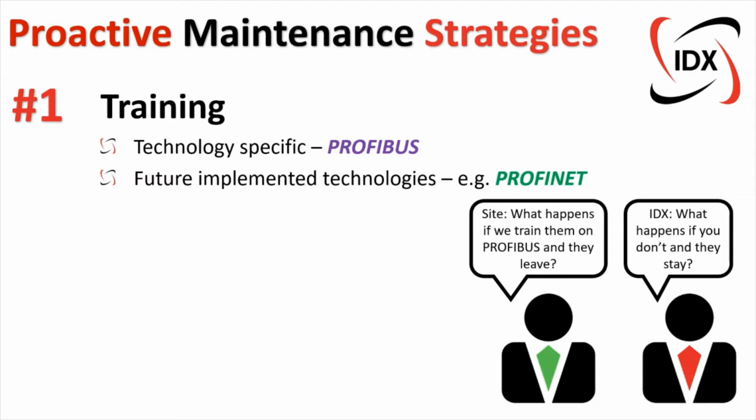And that's pretty important, because I think one of the biggest downfalls which PROFIBUS has suffered in the past is that it is installed badly outside of the guidelines, and that ends up causing failures. And unfortunately, it's given the technology at some instances maybe a bad reputation that PROFIBUS doesn't work. And I can promise you today, PROFIBUS works perfectly well if it's installed well from the beginning. It'll never give you an ounce of loss of sleep. So hopefully we can do the same, learn how to properly implement PROFINET and alternative industrial Ethernet technologies going forward to make sure that we install them correctly from the beginning.